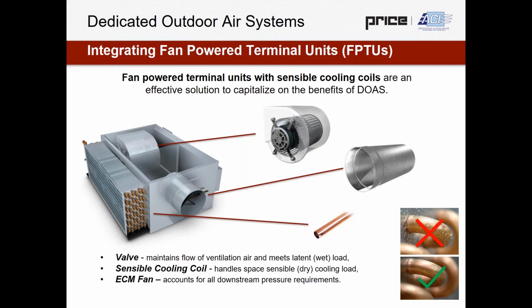And we have that cross flow sensor, so we're going to be able to get really quality airflow measurement, and we're going to be able to modulate that airflow with a butterfly damper. The sensible cooling coil handles space sensible dry cooling loads, and it does that very effectively, considering how large that coil can be, generally selected at 6 or 8 rows of coil depth and a very large coil face area. And then the last piece is that ECM fan, which is accounting for all downstream pressure requirements. It's accounting for air pressure drop through filters and through the sensible coil. So really all components of air distribution for a DOAS system are handled by this box.